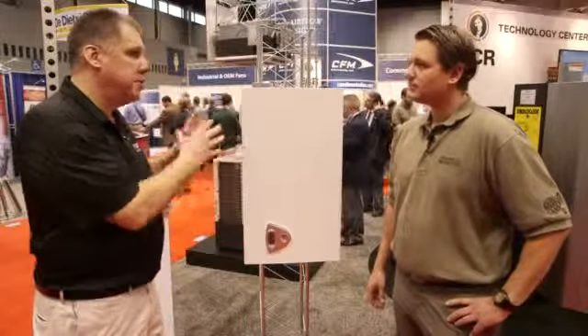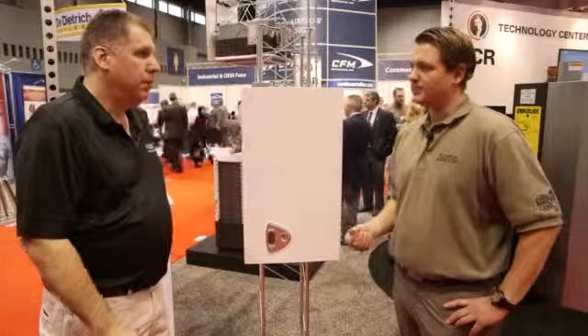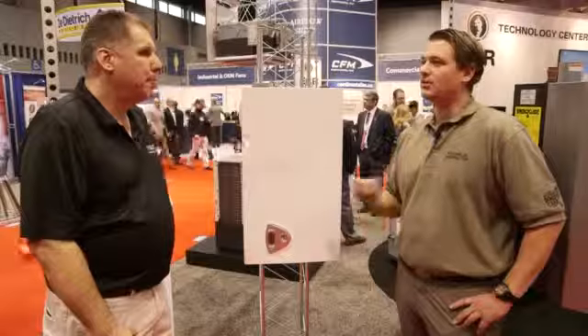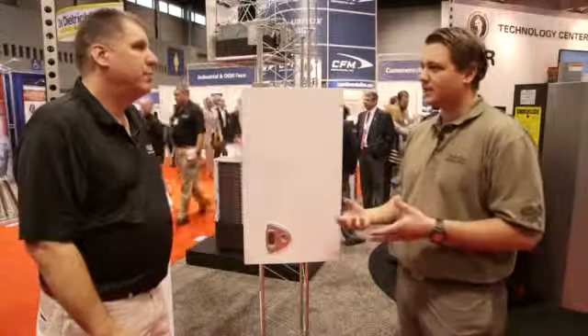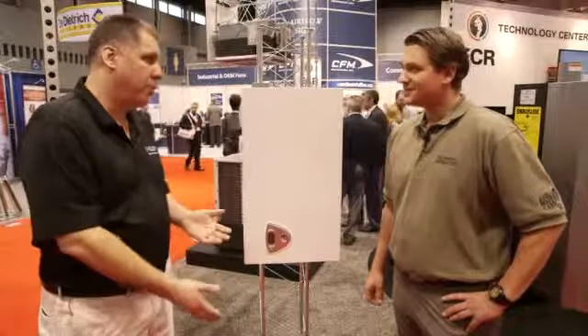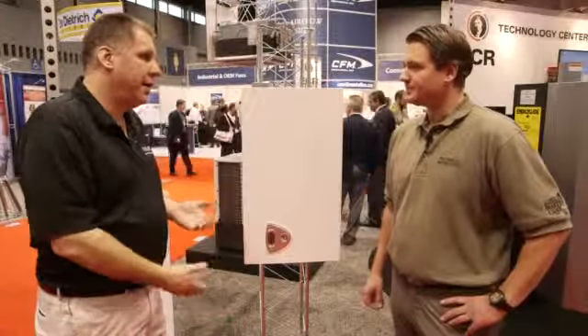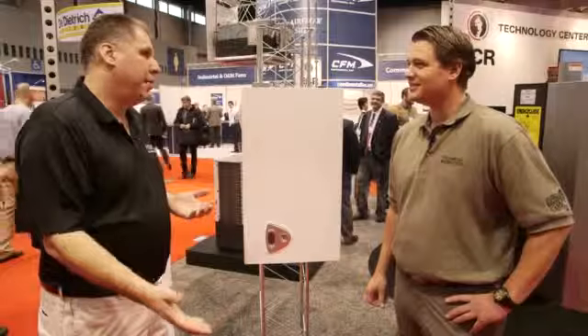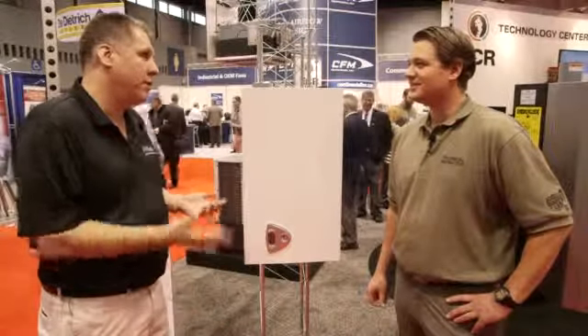And is this a modulating? It's a full modulation of 3-to-1 turn down. But not condensing? Non-condensing boiler. One thing nice about not having condensing is you don't have to worry about putting in a condensate pump, what to do with it, and the yearly maintenance is easier. Right. No, we're in a lot of basements where there's no floor drain or even a set tub. Even if you had a pump, you can't easily pump the condensate to an internal drain, and of course you know what happens if you pump it outside, it's going to freeze up on you.